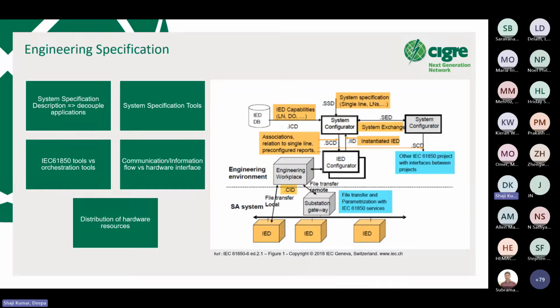The distinction between the two engineering processes is that in specification, the required application functions are denoted by logical nodes, which are assembled into virtual IEDs. During system configuration, logical nodes are linked to real IEDs using the IED capability description, or ICD file. This phase concludes with the comprehensive system description, the SCD file, which contains all essential details needed for information interchange within the network.